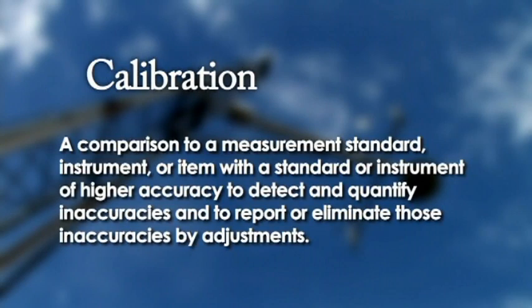Before we get going, let's define what we mean by a calibration. EPA defines a calibration as a comparison to a measurement standard, instrument or item with a standard or instrument of higher accuracy to detect and quantify inaccuracies and to report or eliminate those inaccuracies by adjustments. So, you can see that there are two parts of this process, primarily the measuring to conformance and secondly the adjustment to that conformance. What this translates to is testing and adjusting the instrument to see if it meets our standards.